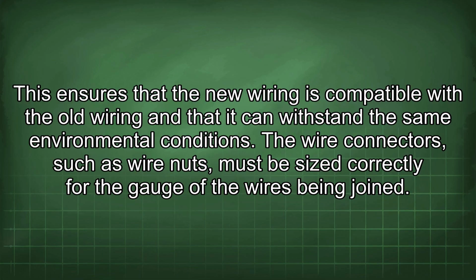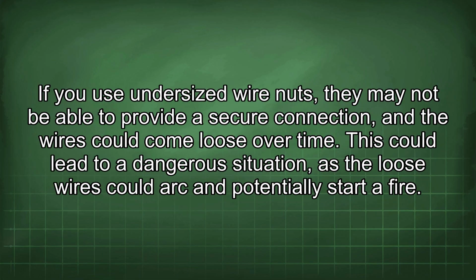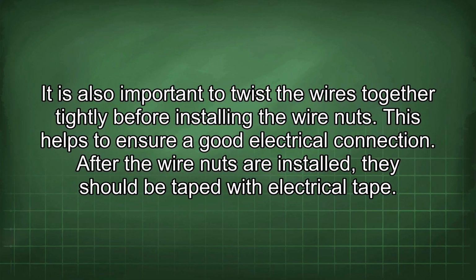The wire connectors, such as wire nuts, must be sized correctly for the gauge of the wires being joined. If you use undersized wire nuts, they may not be able to provide a secure connection, and the wires could come loose over time. This could lead to a dangerous situation, as the loose wires could arc and potentially start a fire. It is also important to twist the wires together tightly before installing the wire nuts. This helps to ensure a good electrical connection. After the wire nuts are installed, they should be taped with electrical tape.